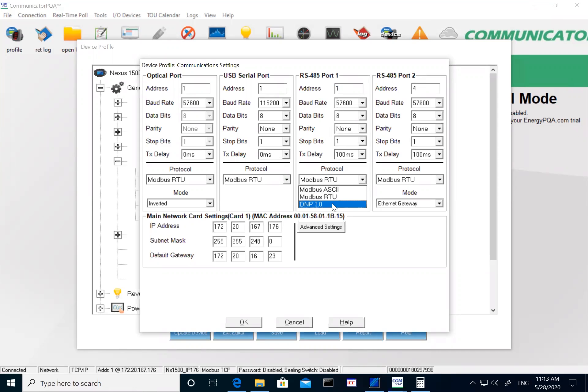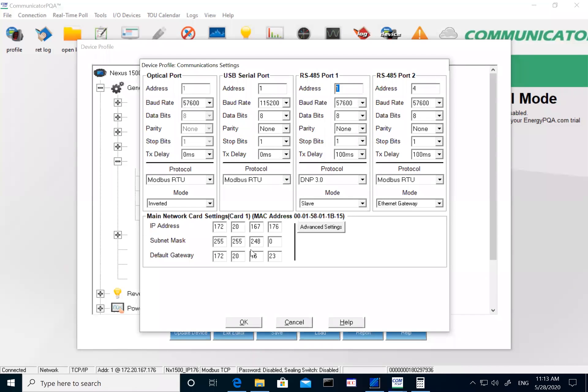For example, I'll use port one as my DNP port. I would set up my protocol, baud rate, device address, data bits, parity, and stop bits here. On the bottom you can set up the IP address — so if you're using the meter for DNP over Ethernet, this is where the meter IP address would be set up.